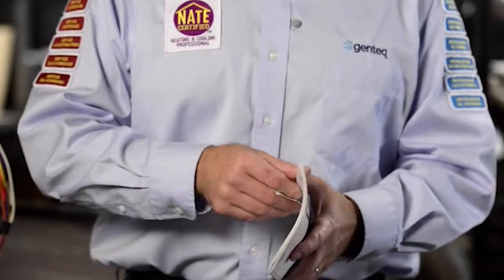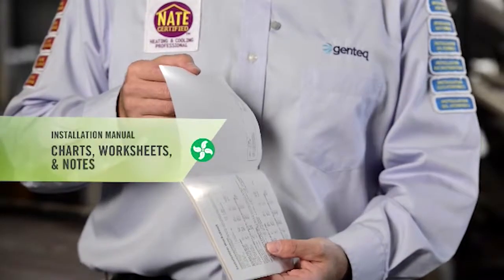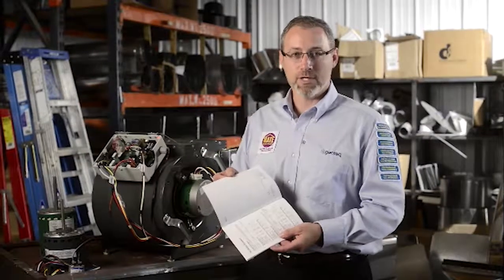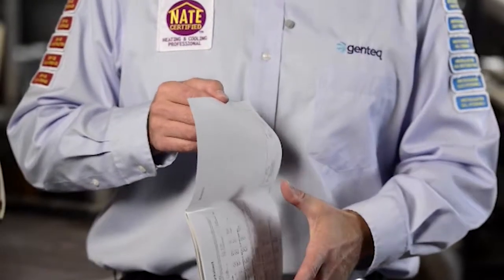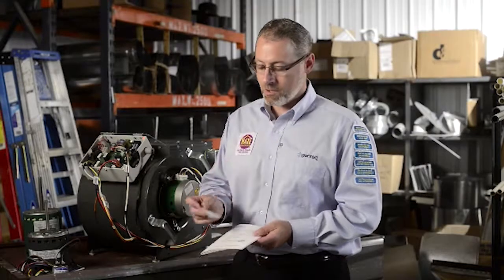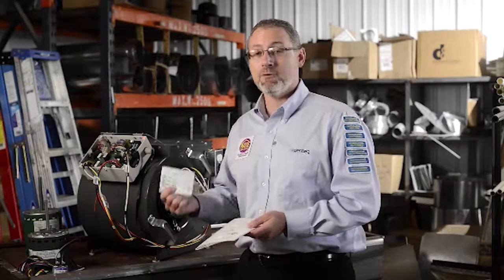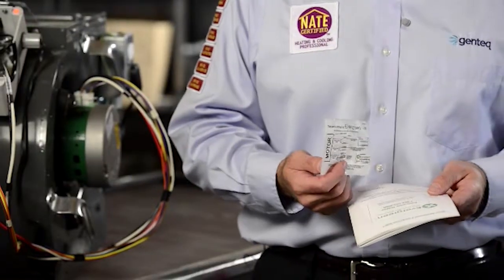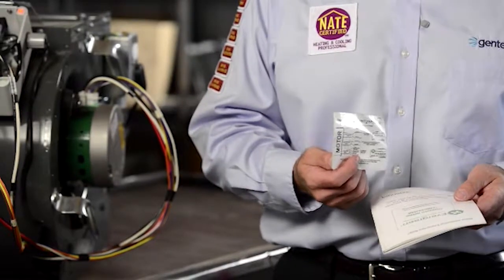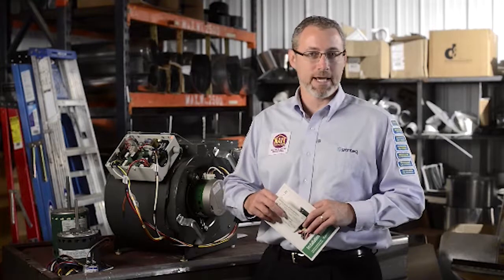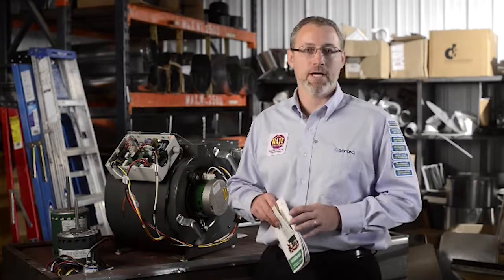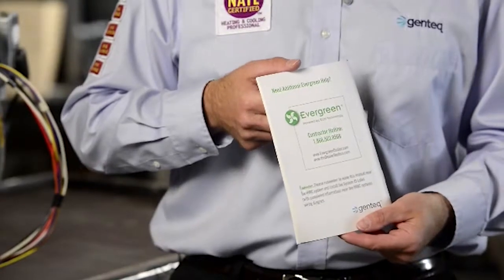Everything we just covered can be found in the installation manual that's included with all Evergreen IM motors and can be found on our website, thedealertoolbox.com. In addition, we've moved all of the charts that we discussed to the back of the book for a quick reference guide: the motor selection chart, the horsepower selection chart, some worksheets, and even some airflow charts and some notes areas if needed. In the manual, as well as on the ID label, as well as on the motor label, is the schematic for the entire motor harness. This should make installing Evergreen IM very easy. And last but not least, should you need any diagnostic support, there's 3 pages of diagnostic guides in the back of the manual and our 800 tech support number on the back cover.